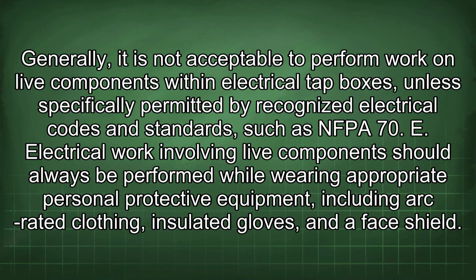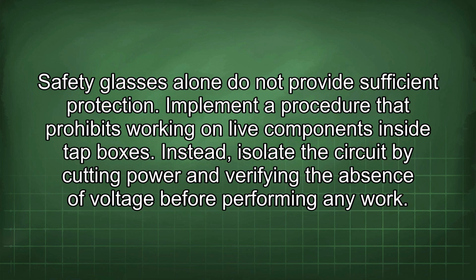Generally, it is not acceptable to perform work on live components within electrical tap boxes unless specifically permitted by recognized electrical codes and standards such as NFPA 70. Electrical work involving live components should always be performed while wearing appropriate personal protective equipment, including arc-rated clothing, insulated gloves, and a face shield. Safety glasses alone do not provide sufficient protection.